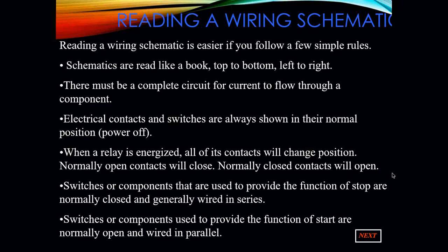Each contact and switch are drawn in their normal position. Every time you look at a wiring diagram, it is shown with the power off. We have to read a wiring diagram and we have to use our imagination to visualize once power is applied to this schematic, what is going to happen. That is the most critical part to understanding and reading a schematic, is being able to use your imagination to say, okay, if I close my switch or my thermostat, what happens next?